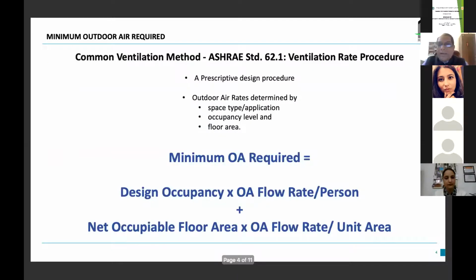So why are our systems not designed to match the higher outdoor air requirement? Most of the systems are designed for the minimum outdoor air required based on the ASHRAE Standard 62.1 ventilation rate procedure. This is a prescriptive procedure, which depends on a few factors like the space type, space application, occupancy level, floor area, and of course ventilation effectiveness. And a very simple calculation can determine the minimum outdoor air required.